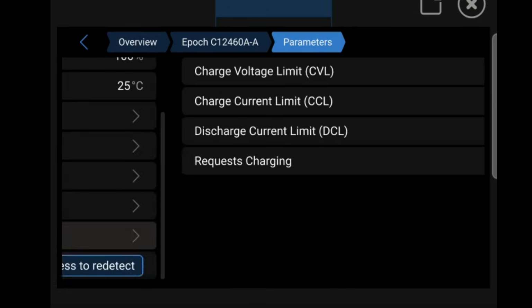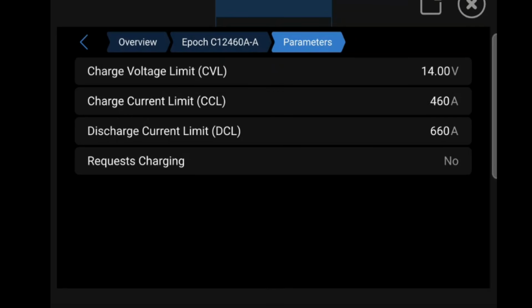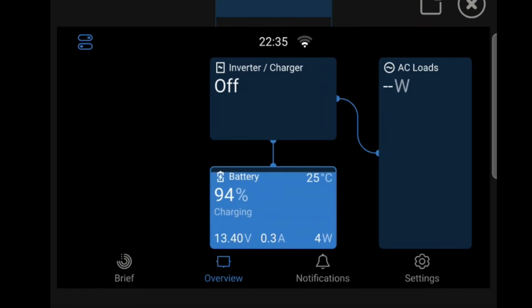If we go to parameters, these are the details from the BMS commanding the Victron system. For instance, the charge voltage limit right now is 14 volts. If we applied a charge source - a MultiPlus, Quattro, DC to DC charger, or Victron MPPT - it would command those units to output 14 volts, charging to 14 volts absorption, holding there for some time, then dropping to a lower float voltage of 13.5. Charge current limit is 460, discharge current limit is 660, and there's no request for charging at the moment since we don't have any charge sources connected. That concludes the easy setup.